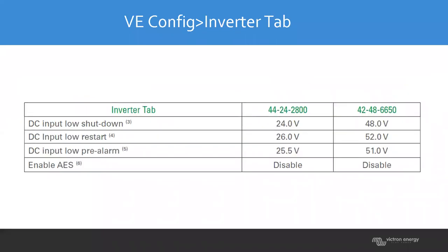Now we'll get into the inverter tab. The DC input low shutdown: 24 volt for the 24 volt system, 48 for the 48. DC input low restart is 26 and 52. DC input pre-alarm would be 25.5 and 51.0 for the 48. Enable AES, we would disable that. This is not referencing the Discover AES batteries. This is another function of Victron, and you could learn more about that on possibly Victron Live.